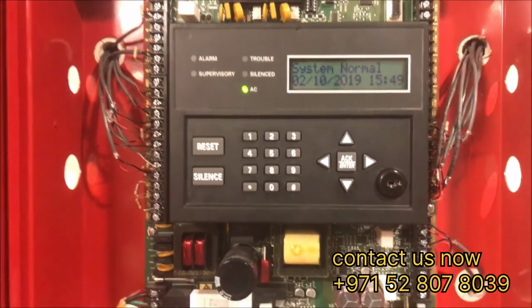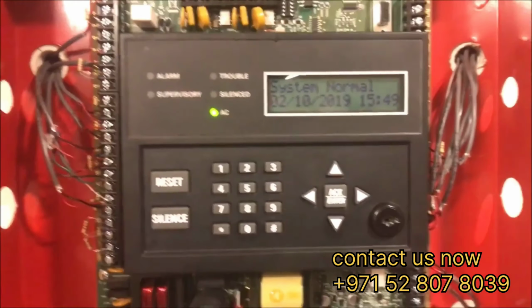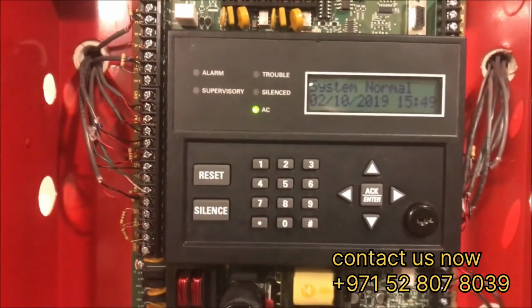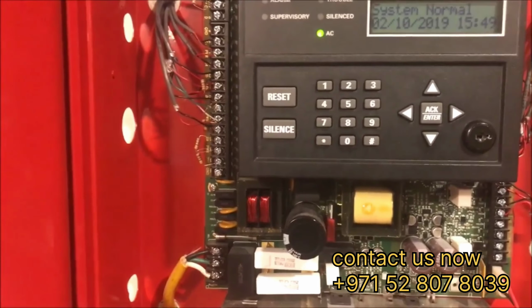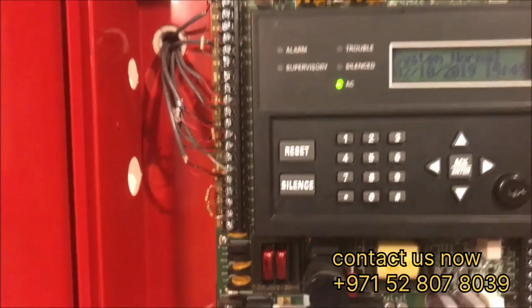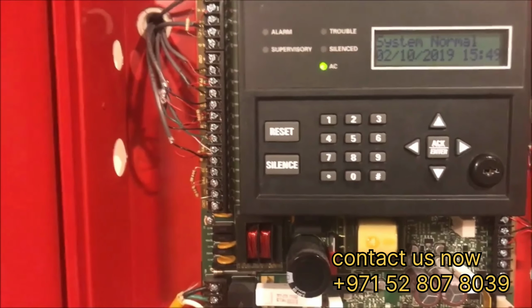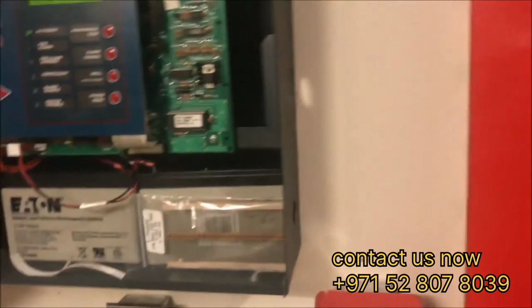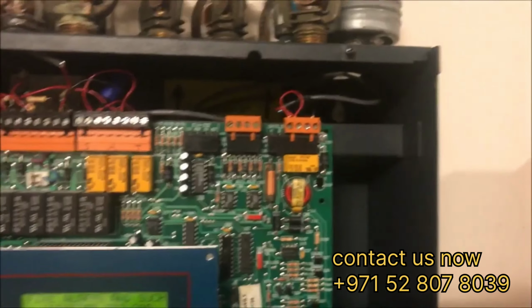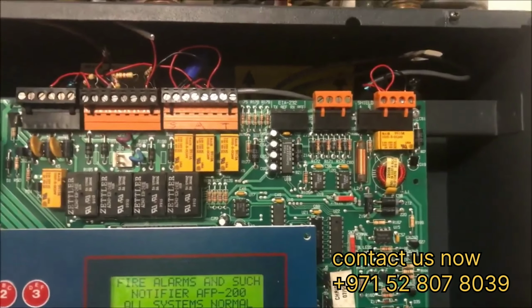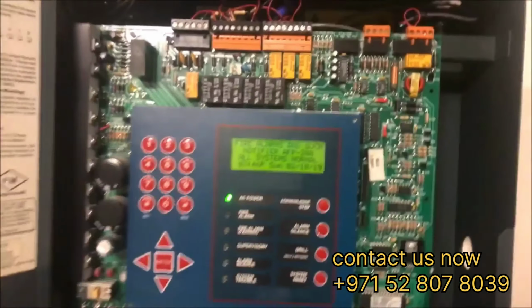Now, what happens is when a zone is activated, you only know that that event is happening in a certain zone, and that zone can range from a stairwell to an entire floor of a building. So that they can be really big zones. Now with an addressable panel, you don't really have zones. You can have grouping zones for different points, but this panel and this panel use points.